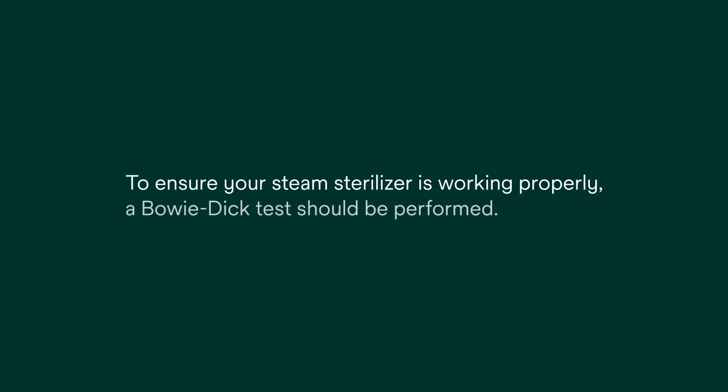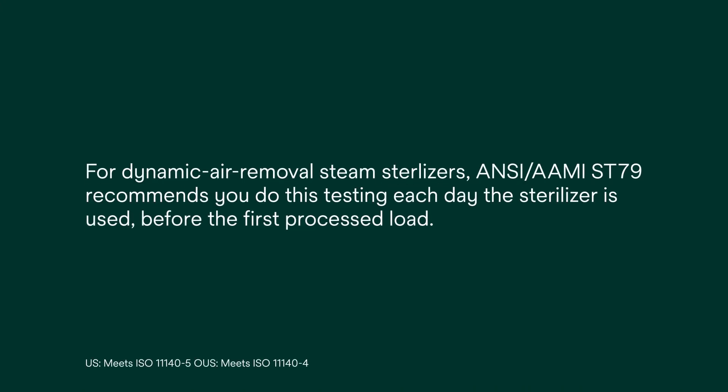To ensure your steam sterilizer is working properly, a Bowie-Dick test should be performed. For dynamic air removal steam sterilizers, ANSI/AAMI ST79 recommends you do this testing each day the sterilizer is used, before the first processed load.